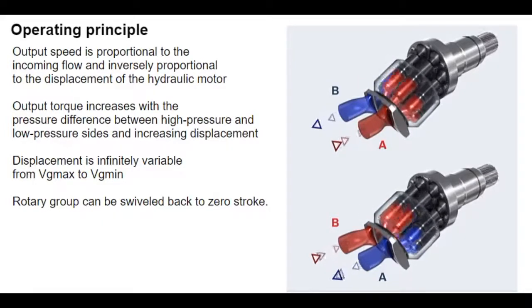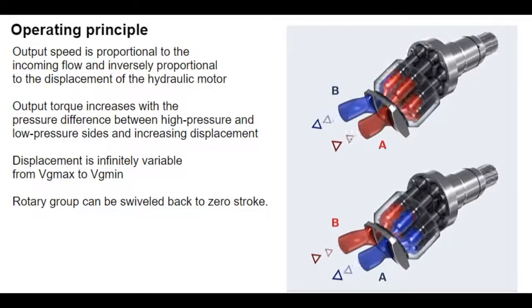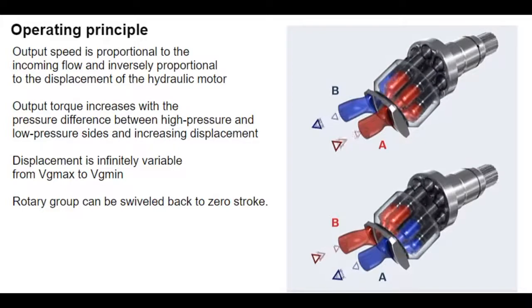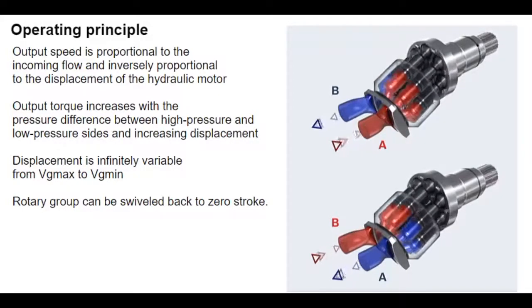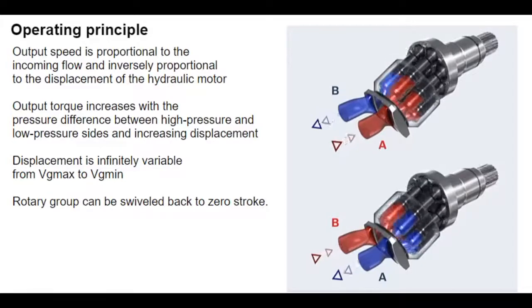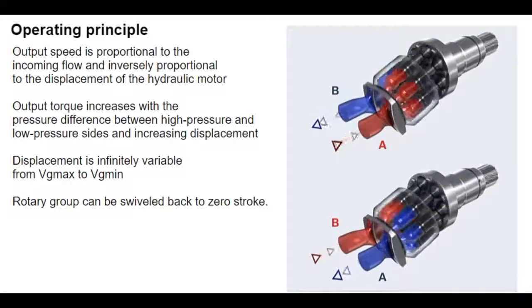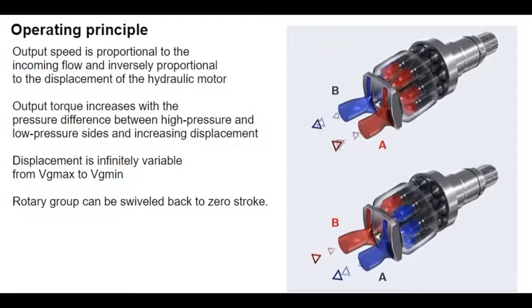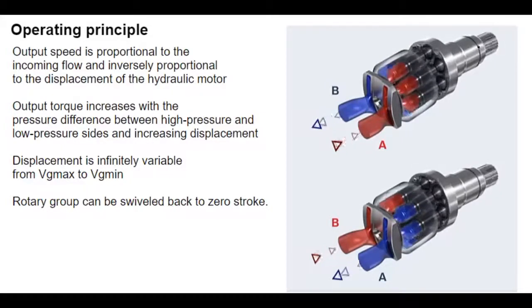Displacement is infinitely variable from VG-max to VG-min. The more the rotary group is swiveled back, the higher the output speed and the lower the output torque. The rotary group can be swiveled back to zero stroke. The direction of output rotation depends on the supply of hydraulic fluid. If it is supplied from the A-side (right), the motor rotates clockwise. If it is supplied from the B-side (left), the motor rotates counterclockwise.